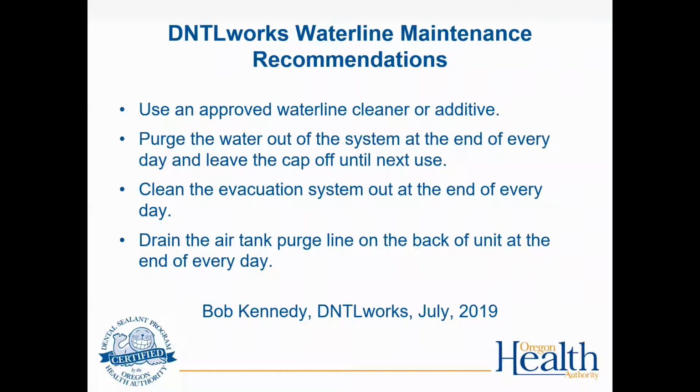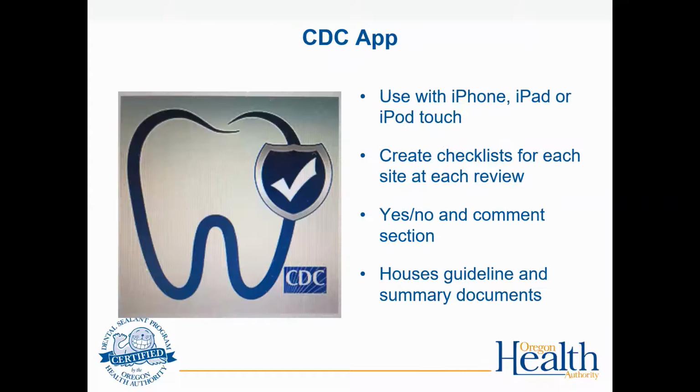And this is information about the water lines, and this is from Bob Kennedy at DNTLworks. Use an approved water line cleaner additive. Purge the system at the end of every day and empty the bottle and leave the cap off until next use. Clean out the evacuation system each day with something like Maxivac, and drain the air tank and purge the line at the end of each day.